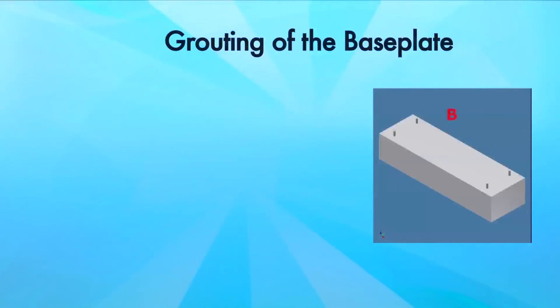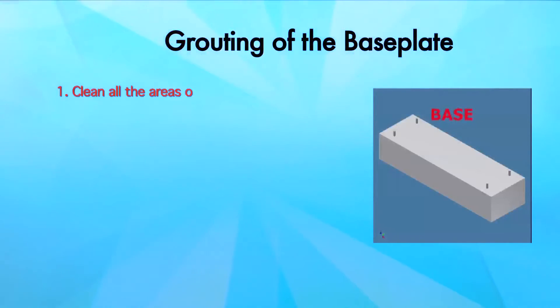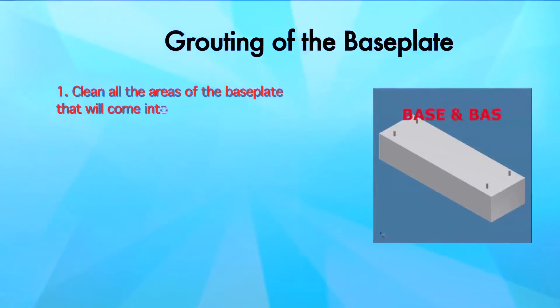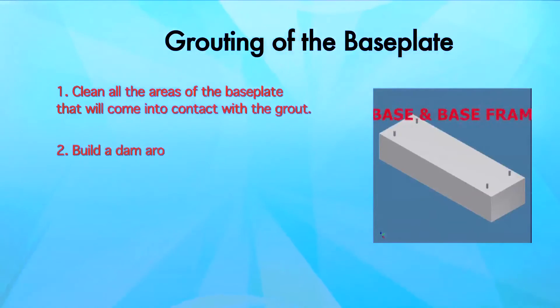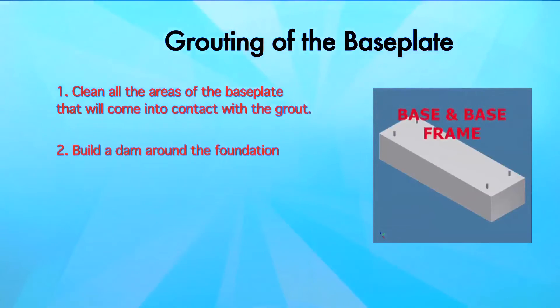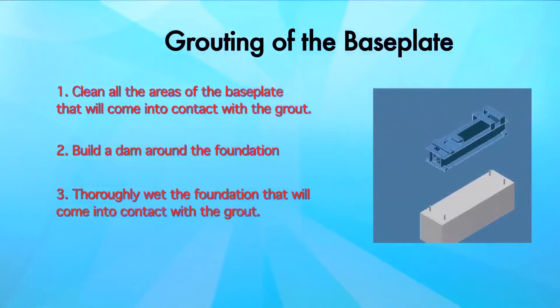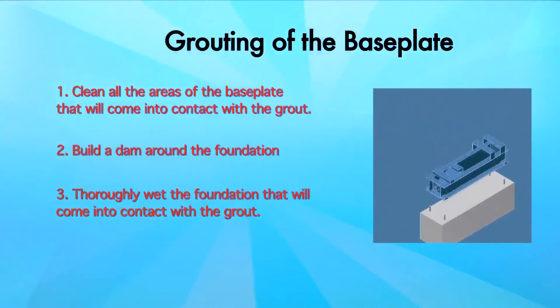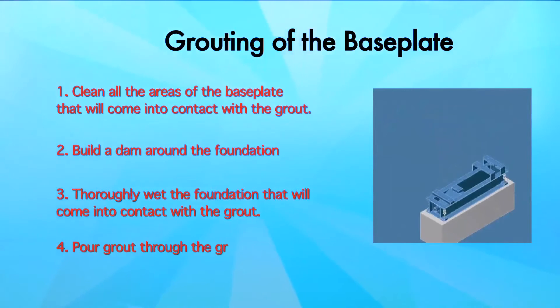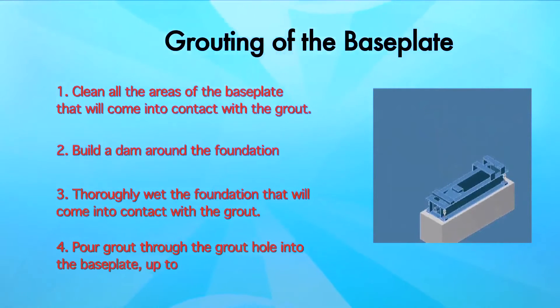Grouting of the base plate. Step 1: clean all the areas of the base plate that will come into contact with the grout. Step 2: build a dam around the foundation. Step 3: thoroughly wet the foundation that will come into contact with the grout. Step 4: pour grout through the grout hole into the base plate up to the level of the dam.